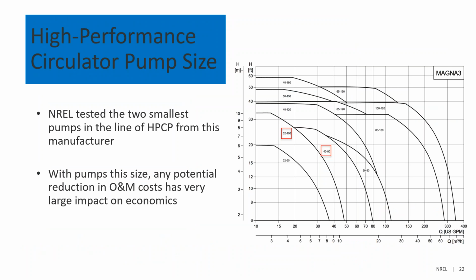So the ones that we tested for this GSA project were actually the two smallest pumps that are manufactured by this particular manufacturer. You can see on this graph, they offer a number of different models for this particular pump. For example, in certain applications where you have really large flow rates but relatively low head pressure, you can get up to over 300 gallons per minute.